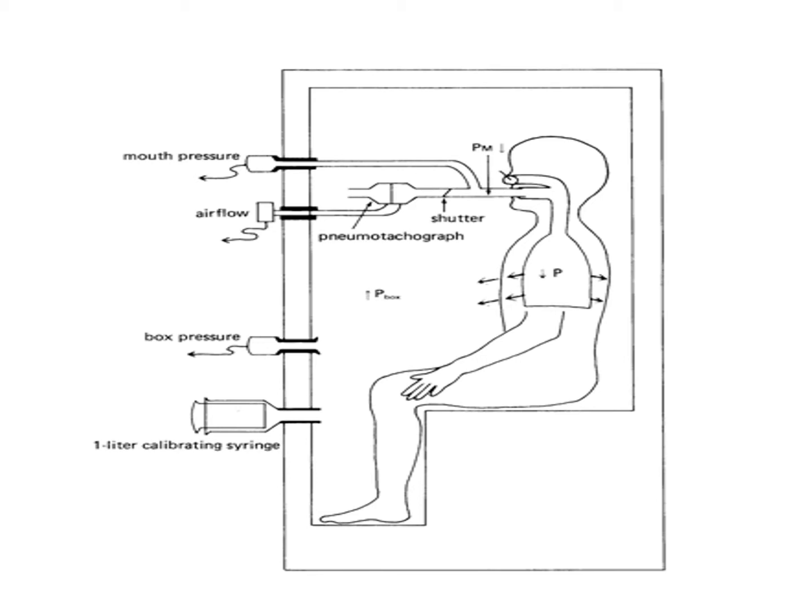It consists of a rigid cup or chamber placed over any part of the body, normally a limb or digit, in which the volume changes are to be measured. The cup is tightly sealed to the member, and changes in the volume reflect the pressure changes of air inside the chamber. Thus, by measuring pressure change at constant volume conditions or measuring volume change at constant pressure conditions, we can make useful measurements.